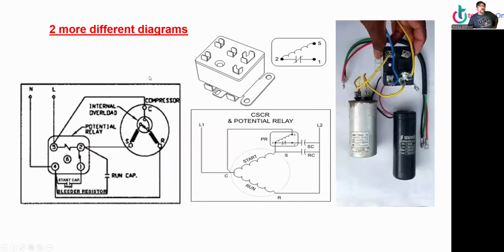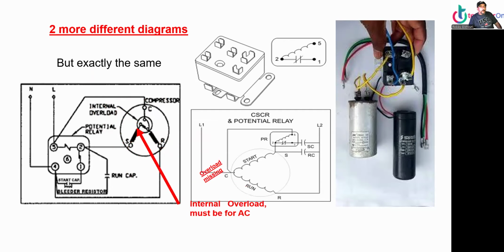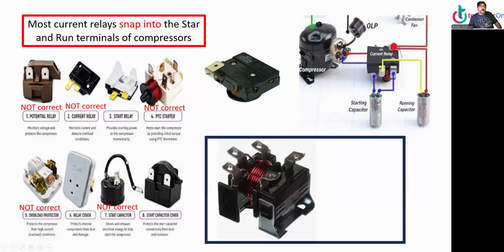And guess what? 2 more diagrams. There we go. 2 more diagrams showing exactly the same thing, but one of them doesn't have overload. It looks like, yep, that one doesn't have overload. Capacitor start, capacitor run. The same thing as a compressor. But overload missing. Alrighty. Oh, that one has internal overload. That's right, that one has internal overload because it's inside. Must be an air conditioner. Alrighty. Now let's move on to the current relay.